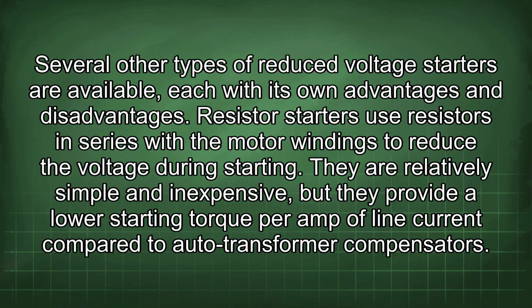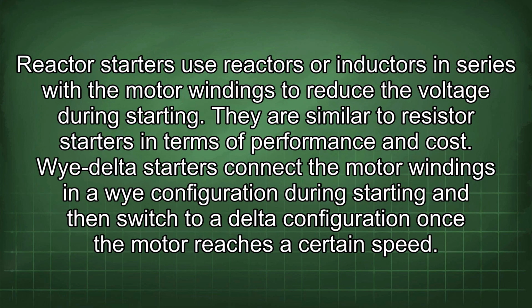Several other types of reduced voltage starters are available, each with its own advantages and disadvantages. Resistor starters use resistors in series with the motor windings to reduce the voltage during starting. They are relatively simple and inexpensive, but they provide a lower starting torque per amp of line current compared to autotransformer compensators. Reactor starters use reactors or inductors in series with the motor windings to reduce the voltage during starting. They are similar to resistor starters in terms of performance and cost.